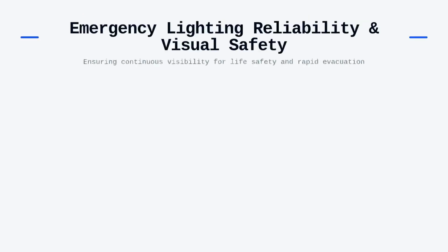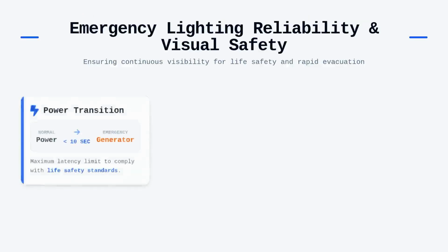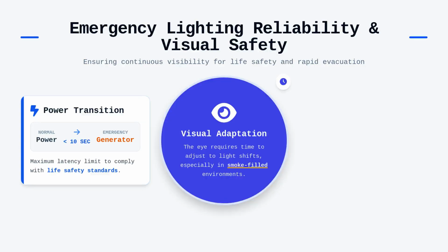The reliability of these systems often hinges on the transition phase between normal power and the emergency source. When utilizing an emergency generator, the transfer switch must operate within a maximum latency of 10 seconds to comply with the standard requirements for life safety illumination. This short window is intentionally narrow to account for human visual adaptation physiology, as the human eye requires time to adjust to sudden shifts in light levels, particularly in the presence of smoke.